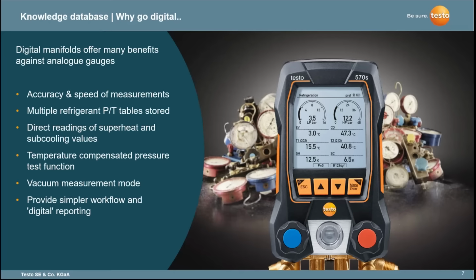You've also got the ability for the device to connect to accessory probes, so we can give you the temperature readings that you would normally get from a separate differential thermometer, and the instrument will also directly calculate your superheat and subcool values and display them in real time. But outside of those functions that the device is offering, which is replacing an analog gauge set, the digital manifolds offer many more test functions.